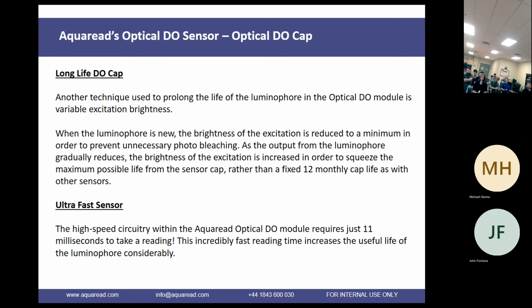The sensor is very fast. As I said earlier, it takes 11 milliseconds to take a reading. That's 11 milliseconds to reach T90, which is the value given for DO sensors.